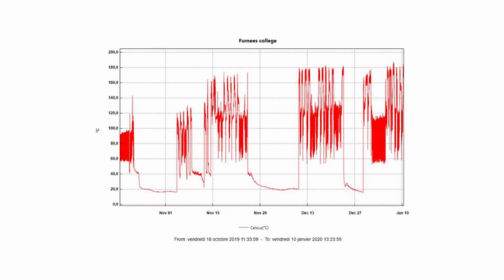It's a powerful tool. The data, the graphs that are produced on there over a month, 6 weeks or longer really identify key issues which wouldn't be possible simply on a half day spent with a service engineer trying to identify some of the problems. It really shows what's actually going on with that boiler and points the way, with a skilled engineer analysing the graphs, to really getting to the bottom and solving a lot of these sometimes very niggly issues as well as some very big issues, and really ensuring that biomass boilers really perform properly.